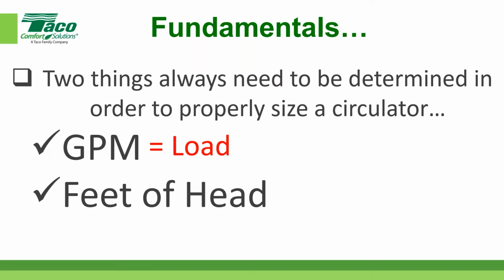20 would be lots of things, some radiant with counterflow spiral, counterflow serpentine. 20 would also be a lot of fin tube baseboard, depending on how many emitters are on the same run, that sort of thing. 20 would be just what they've used for years and years as a standard, a high temperature, 180 going out and coming back at 160, kind of design criteria. When we get into condensing pieces of equipment, well, before I do that, let's talk about panel radiators.